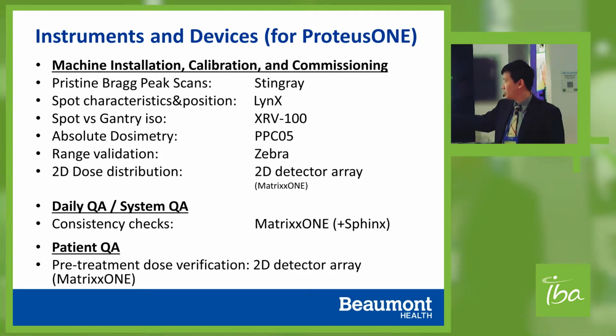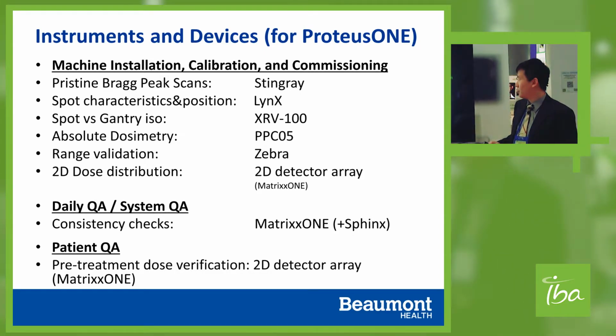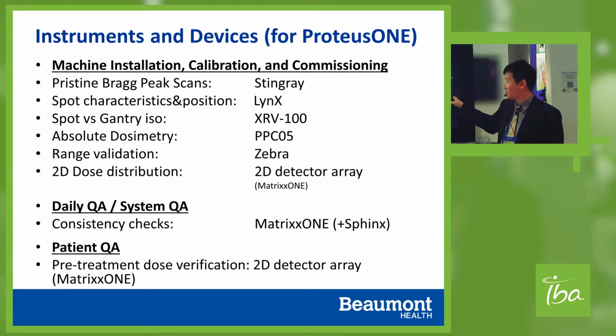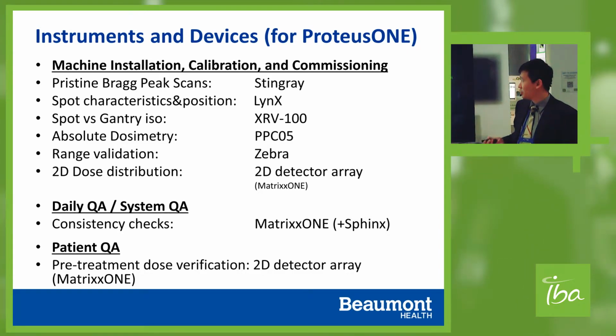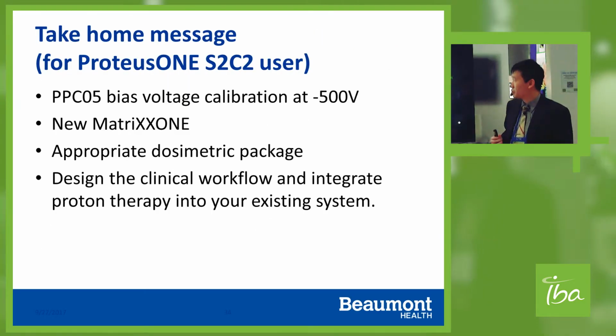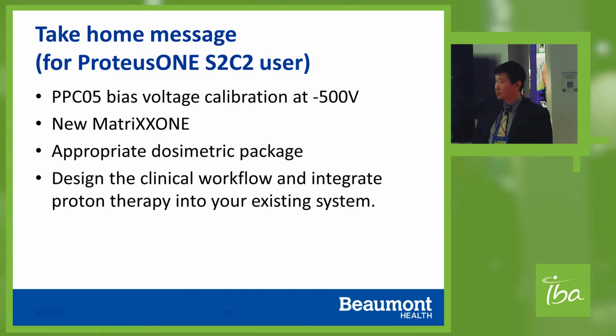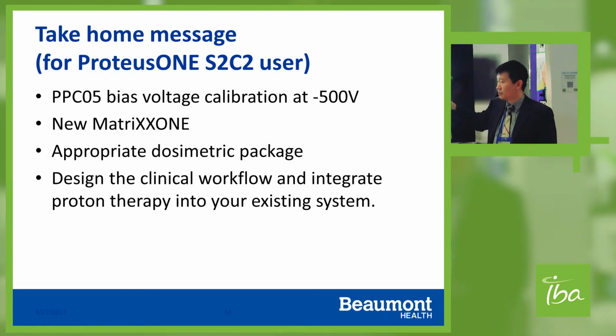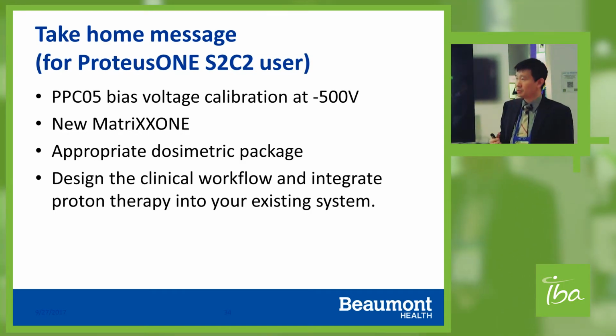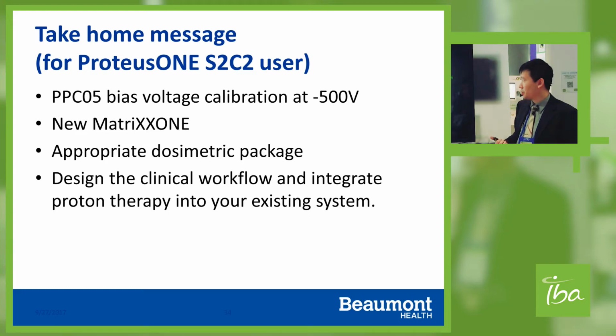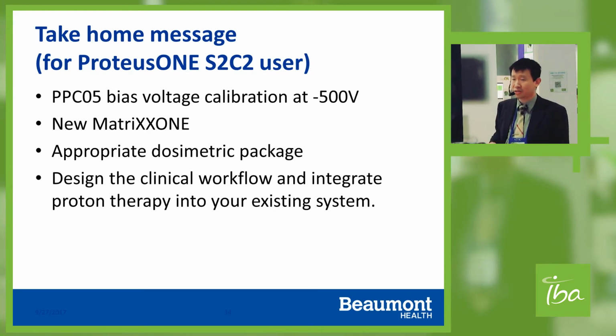So in summary, this is a screenshot you might need for reference to commission the Pencil Beam algorithm, with the PBS nozzle and the proton system, and the Matrix 1 was used for the Proteus One machine. The take-home message, which is really important: first of all, make sure you calibrate your absolute dose with negative 500 volts. We use the new Matrix 1 for your Proteus One because it's a single cyclotron. And an appropriate dosimetry package is also needed, or cross-calibrate with your photon side, to make sure the device is working before you actually start commissioning.